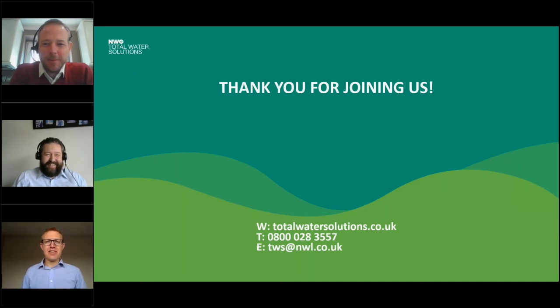We strongly recommend the use of fused spurs without switches as a longer term solution, but that's another story. So we know when it's been unplugged, or we can tell you if it's still connected but the plug's just been switched off. The gateway has a backup battery of, I think, about 6 hours. That gives us enough time to know about the problem, and either let someone on the site know to plug it back in or turn it back on, or for one of the engineers to go and sort it out.